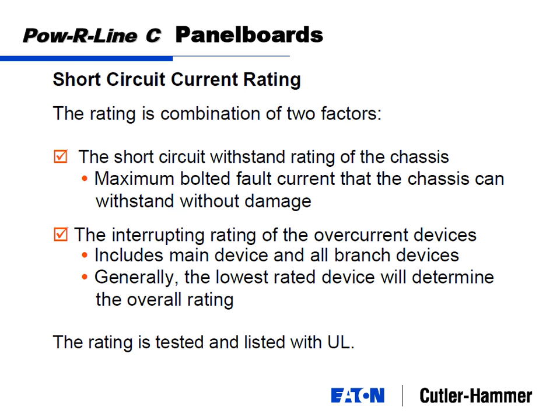When I say interrupting rating, there are two ways. The first one is the short circuit withstand rating, and the second one is the circuit breaker interrupting rating. And these terms are sometimes interchanged or often misunderstood. But when we talk about withstand rating, it's the ability of a panelboard chassis or even a circuit breaker to sit there and handle the fault current without exploding into pieces. In the case of a chassis, it sits and waits while an upstream device may be counting down to a trip.